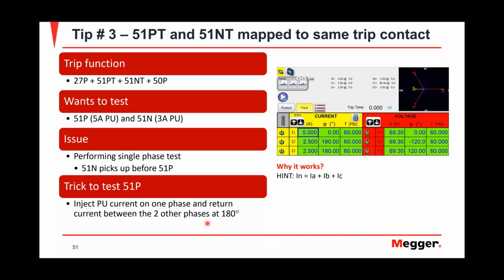So one quick thing that you could do is inject the test value, your pickup value. Let's say you're doing an A phase fault. You inject, let's say, 5 amps is your pickup for your phase, but then you use your B and C currents and cut it in half. So in this case, it's 2.5 on each, both of them at 180. So you split the current going out on A phase and coming back into B and C. That way, this 2.5 is less than your neutral pickup, so your relay will not trip on neutral overcurrent, but it will trip on phase overcurrent. So splitting the current, you inject the fault current on A and coming back on B and C, and do the opposite for all the other phases.